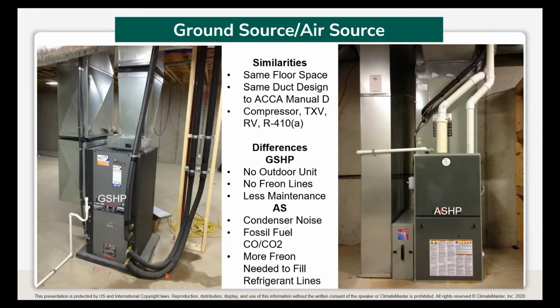You are seeing water on the floor of this new installation because it recently underwent what we'll call a flushing procedure, which is what we do before we commission the piece of equipment. The flushing of our ground loop, and then our heat pump, and then our ground loop and heat pump together is needed to get all of the air out of the system. Air is the enemy of a geothermal heat pump system, and we need to rid the indoor and outdoor portions, both combined, of air.